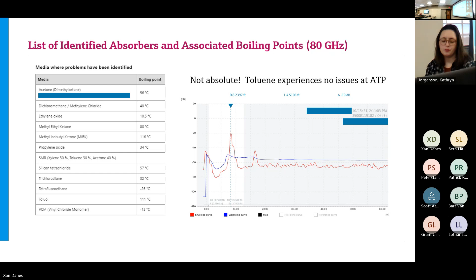Oftentimes, if we're working with a pharmaceutical or chemical company dealing with atmospheric storage or processes that don't get particularly hot, we might educate them that if you end up heating this toluene and approach the boiling point, we could have signal attenuation. It truly becomes an ultra consultative approach where you want to use the best possible instrument for the best performance and the simplest setup over the life. But you have to share details like operating temperature and potential future solvents that could be used in a given tank, since we can't always guarantee a storage tank will have the same solvents year after year. So it ends up resulting in a few additional questions, but also making sure we're doing our due diligence in vetting these installations.